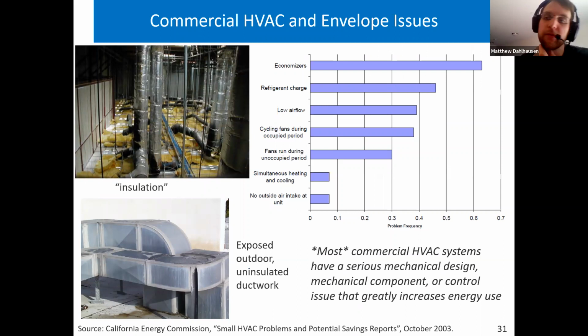So we think that the main source for our lack of diversity in energy use comes from underestimating problems in mechanical design, components, and controls in commercial buildings. In the top left image, you can see an attempt at insulation. This is a dropped ceiling with a conditioned office below. The thermal and air barrier should be this ceiling, but the insulation was moved around and there was no air barrier. If you look closely, you can see an open hole to the outdoors in the background.